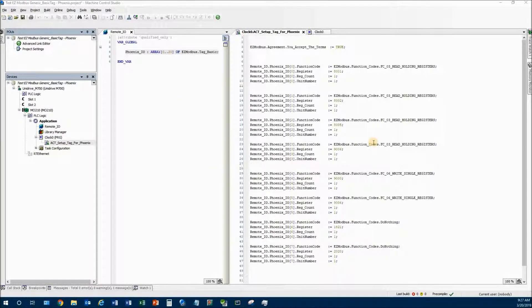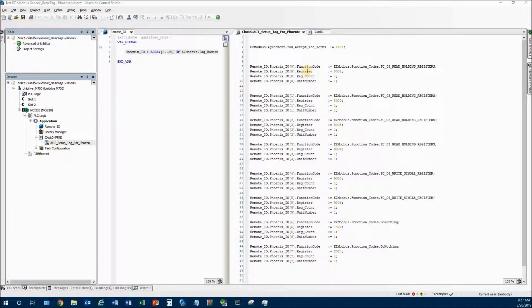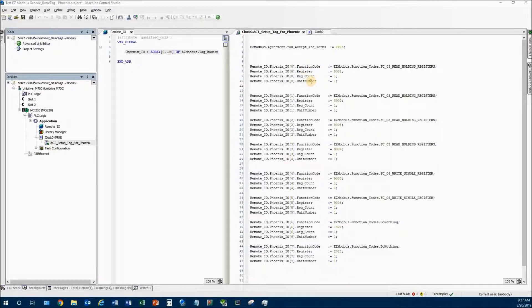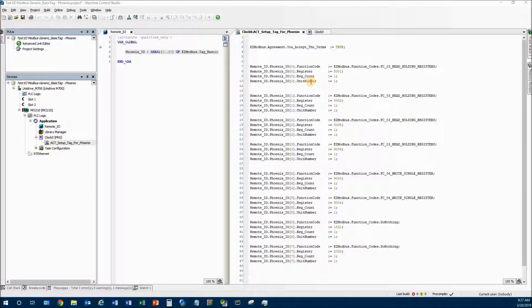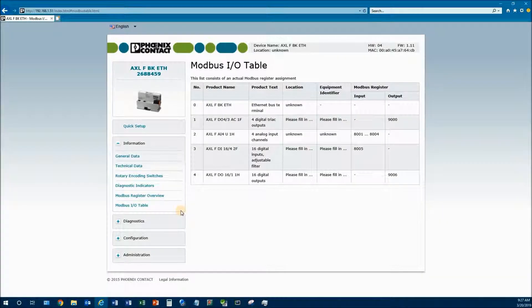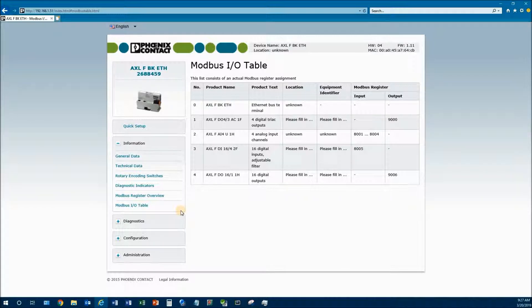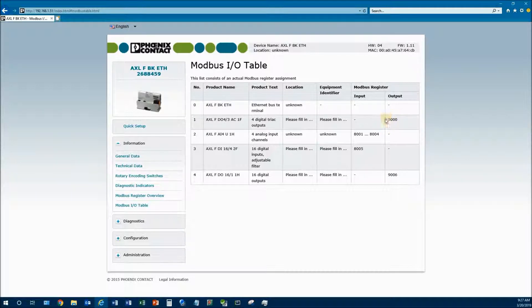The key thing to know is you need to know what function call to use, what register you're going to write to, and the unit number. Most IO block devices are all unit number one because they don't technically use it, but some devices do so you need to be aware. Today we're using the Phoenix, so if I go to the Phoenix IO I showed this in the other video.